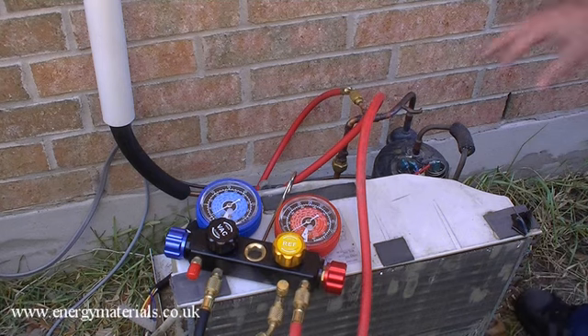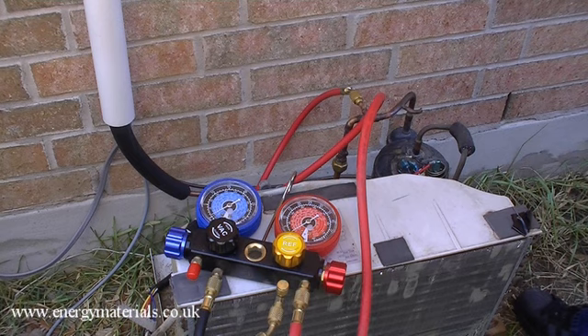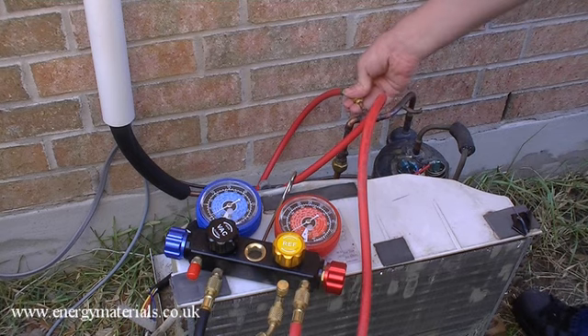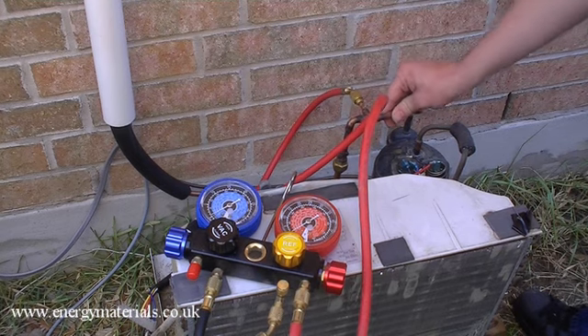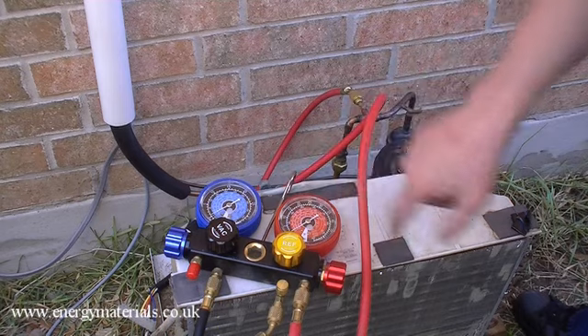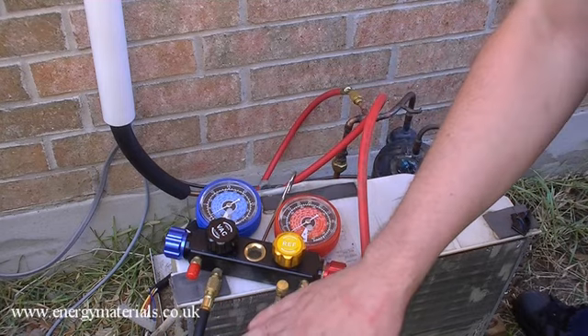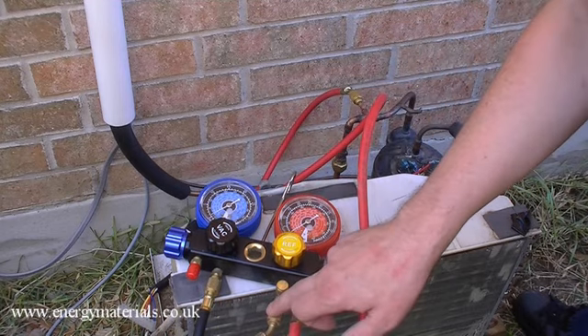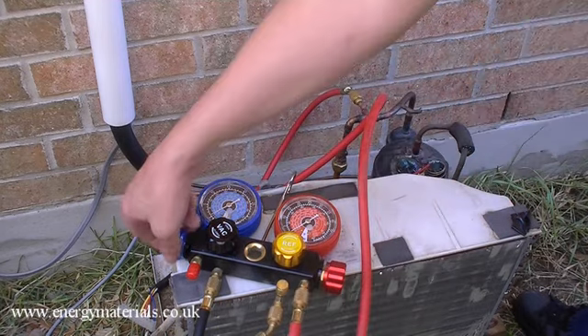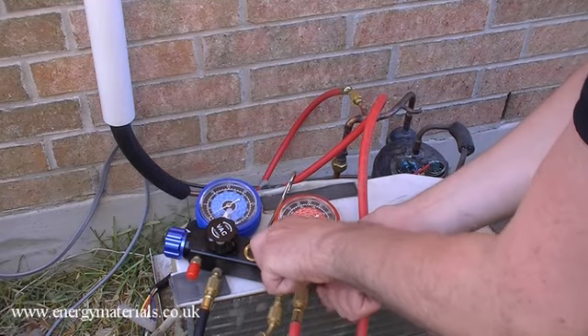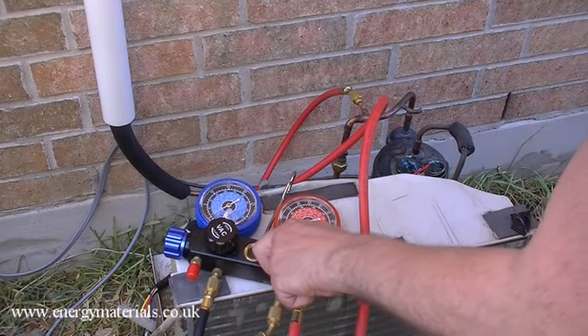Okay, so I think we've brazed all our fittings correctly. So now we're going to pressure test the system. So I've got my high pressure hose connected to the high pressure side of the line set. On my gauge set, I've got a high pressure nitrogen supply on this port, so I'm going to open it up and pressurize my system.